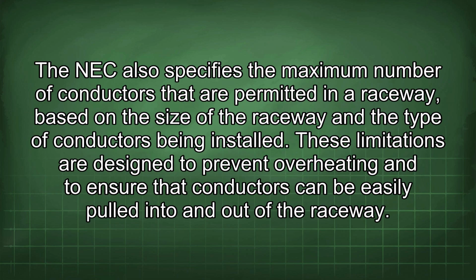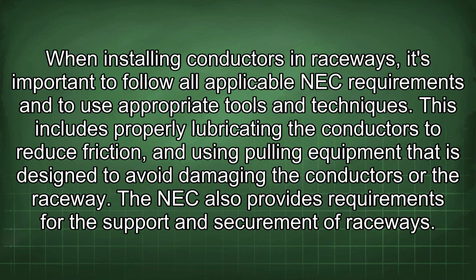The NEC also specifies the maximum number of conductors that are permitted in a raceway, based on the size of the raceway and the type of conductors being installed. These limitations are designed to prevent overheating and to ensure the conductors can be easily pulled into and out of the raceway. When installing conductors in raceways, it's important to follow all applicable NEC requirements and to use appropriate tools and techniques. This includes properly lubricating the conductors to reduce friction and using pulling equipment that is designed to avoid damaging the conductors or the raceway.